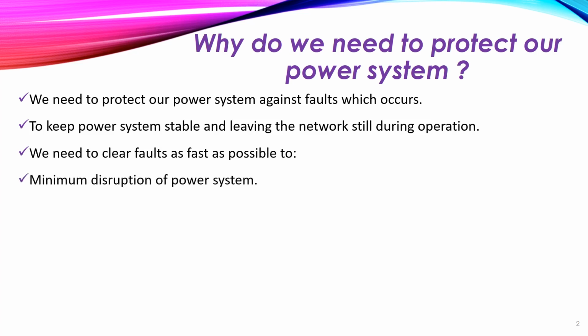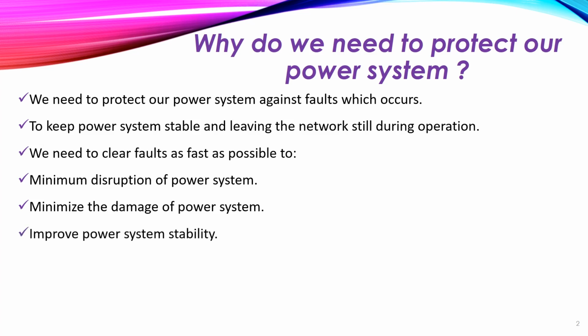Why? In order to, number one, minimize the disruption of the power system itself. Also, minimize the damage of the power system. Because if, for example, a short circuit occurred, the time for which the short circuit persists should be very, very small, in milliseconds. Because if we let this short circuit persist for a couple of seconds, our power system will be damaged. The conductors will break down and fire will occur, and we will lose a lot of money. We will also need to clear the faults in order to improve the power system stability.